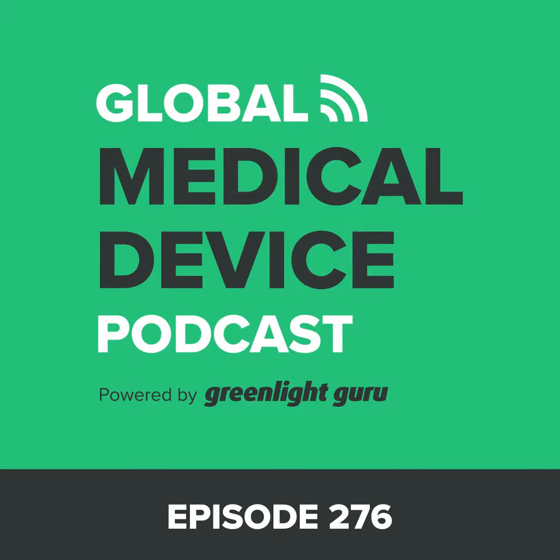Just a few of the points I personally took away from this conversation were, number one, UDI in the EU requires nearly double the attributes as the US's GUDID, but there are tools out there to make that transition much smoother. Number two, if you understand why this initiative took place for UDI, it becomes much easier to implement. The user of this product should be able to clearly and easily identify the device. And while there is complexity with manufacturing, you aren't the first one to go through this. It can be done. Third, there is an ultimate guide to UDI on the horizon, so definitely check out the show notes.